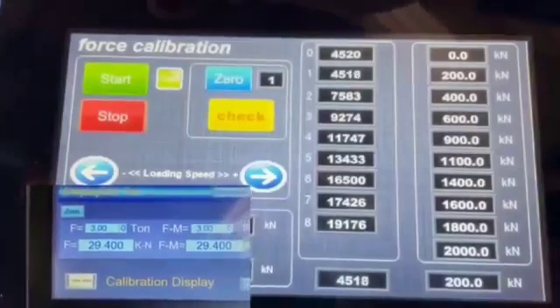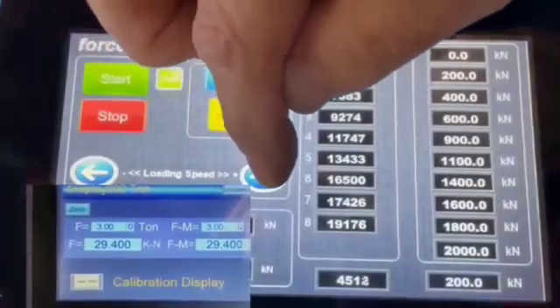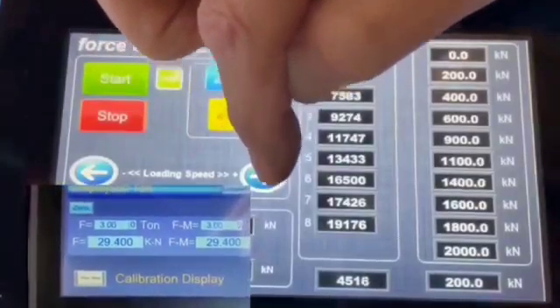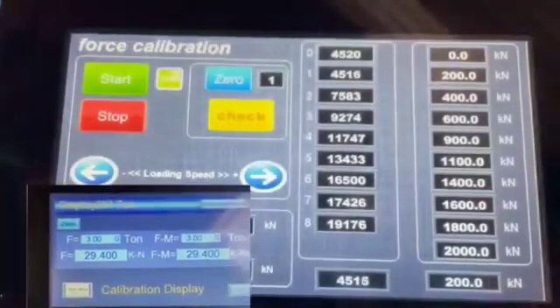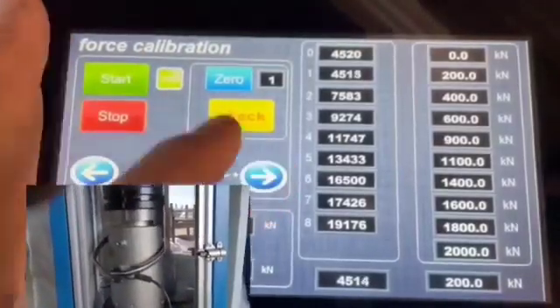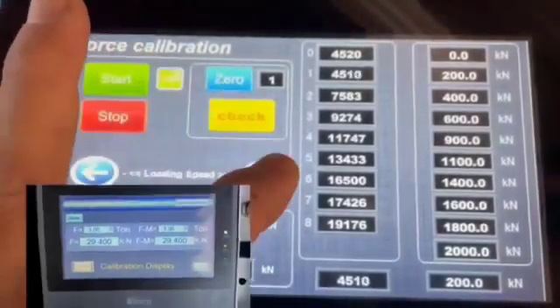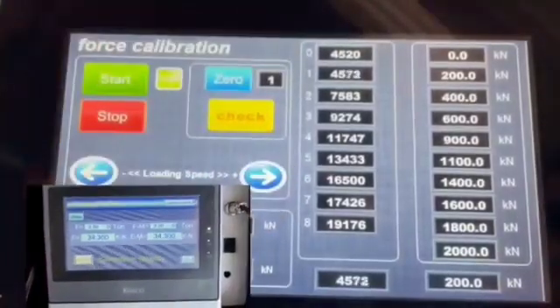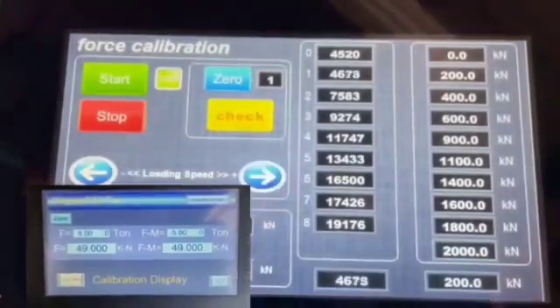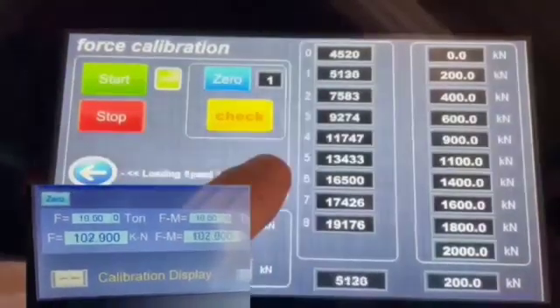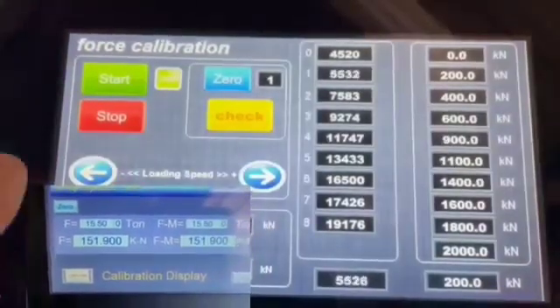The number is 200 kilonewtons, so I'm going to calibrate 200 kilonewtons. I'm reading the load cell on the left side. As soon as it gets to 200, I'm going to push the button to set the second point on my table.